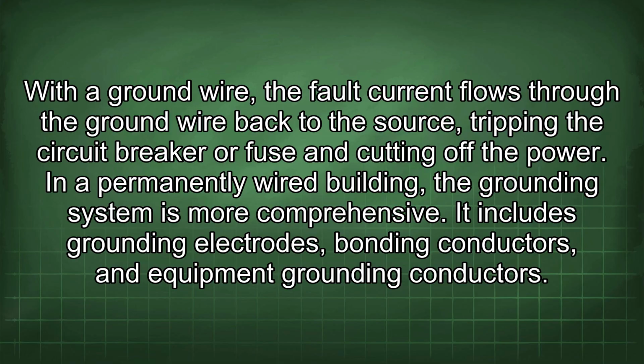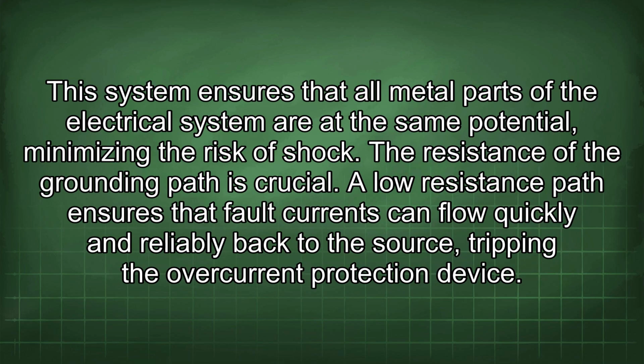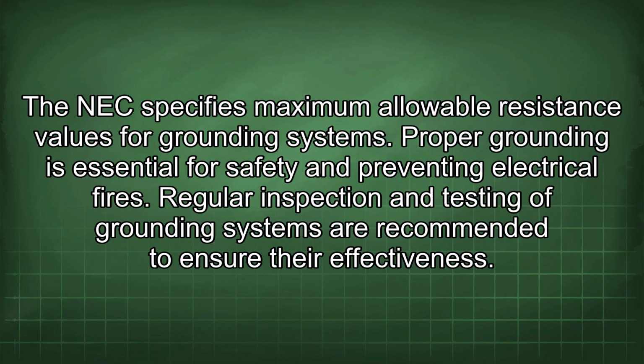In a permanently wired building, the grounding system is more comprehensive. It includes grounding electrodes, bonding conductors, and equipment grounding conductors. This system ensures that all metal parts of the electrical system are at the same potential, minimizing the risk of shock. The resistance of the grounding path is crucial. A low resistance path ensures that fault currents can flow quickly and reliably back to the source, tripping the overcurrent protection device. The NEC specifies maximum allowable resistance values for grounding systems.